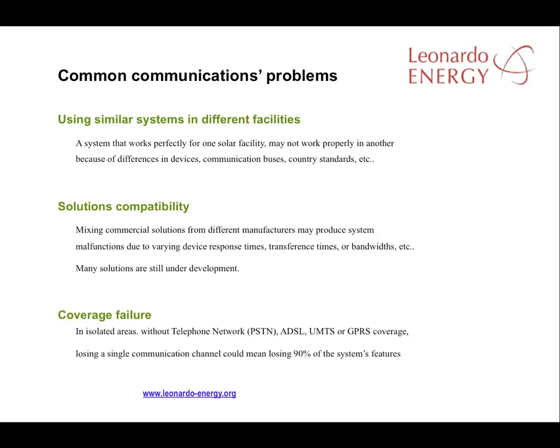Most problems we find in communications in the PV facility come from failed attempts to use the same communication system in different facilities, the incompatibility of solutions at different facilities, and coverage failure. A system that is working properly in one solar facility might not work in another because software may differ when different aged versions are used. The protocols in different countries might also be different; for example, some monitoring equipment may not work in Spain as Spain uses a different protocol to the rest of the world. Sometimes mixing different solutions from different manufacturers may produce system malfunctions. And particularly where the monitoring or remote control of a plant is dependent on cell phone communications, failures in network coverage can have devastating effects.